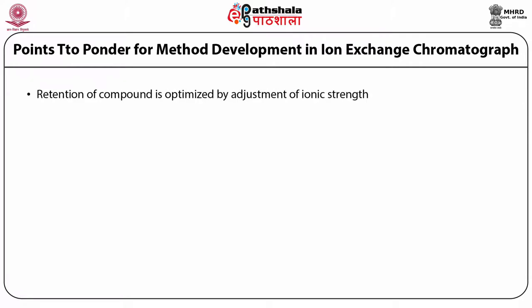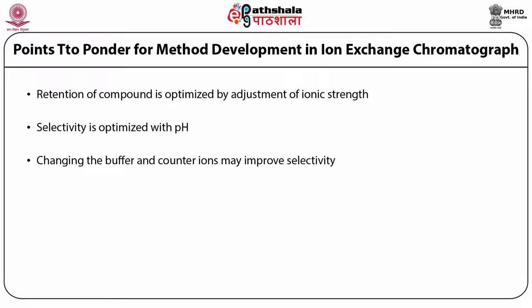After knowing the details of the various components used in ion exchange chromatography, we have to develop a method suitable for analysis of compounds. There are some key points that need to be kept in mind. First, retention of a compound is optimized by the adjustment of ionic strength of the mobile phase. Second, the selectivity is optimized with the pH. Third, changing the buffer and the counter ions may improve the selectivity criteria.